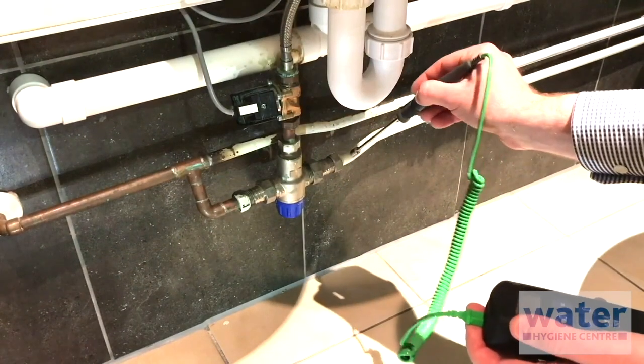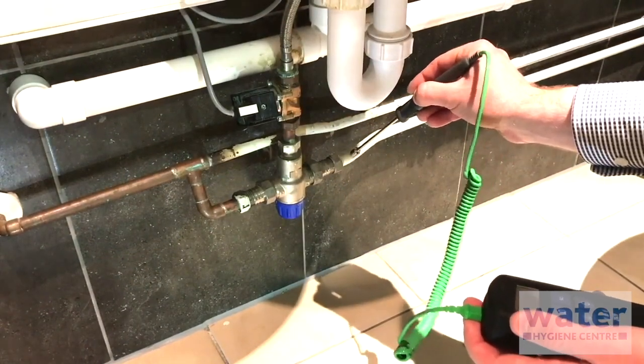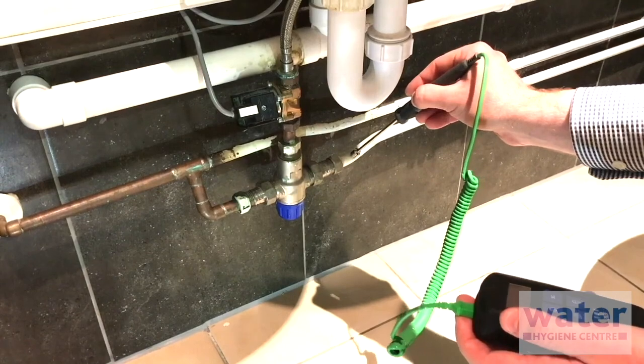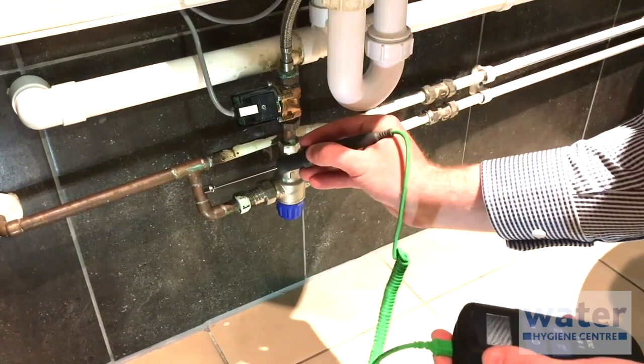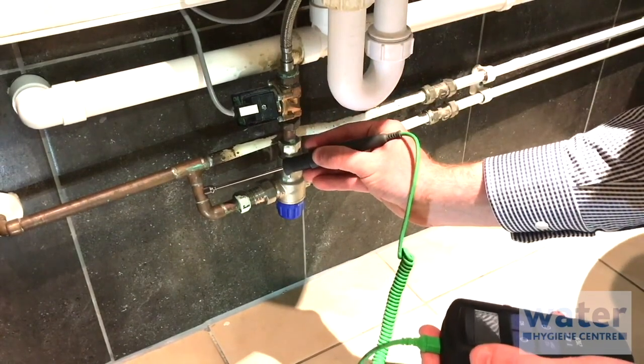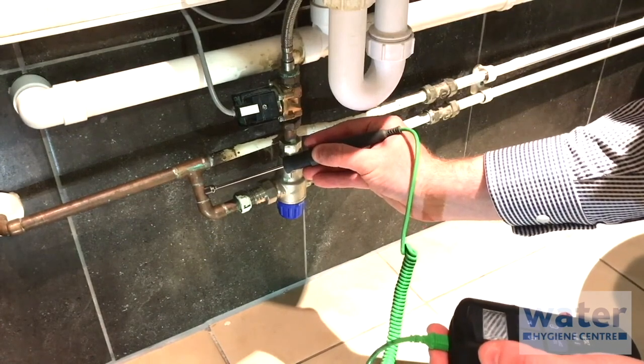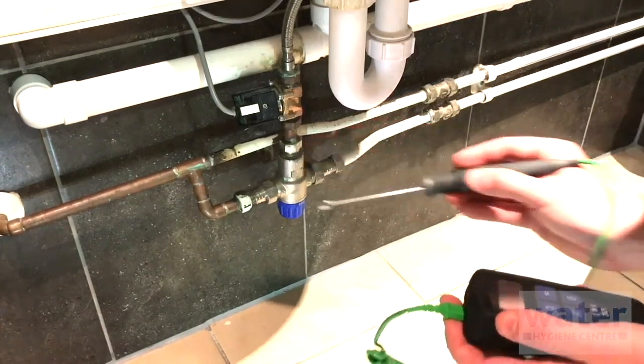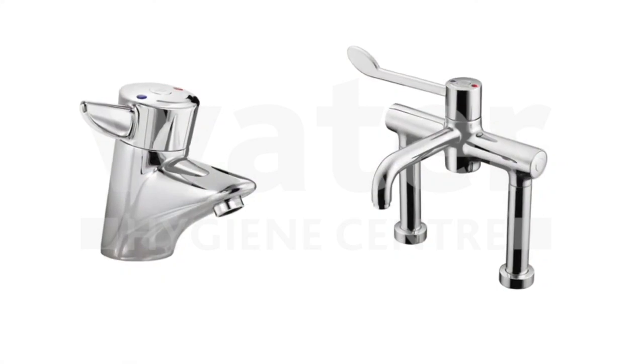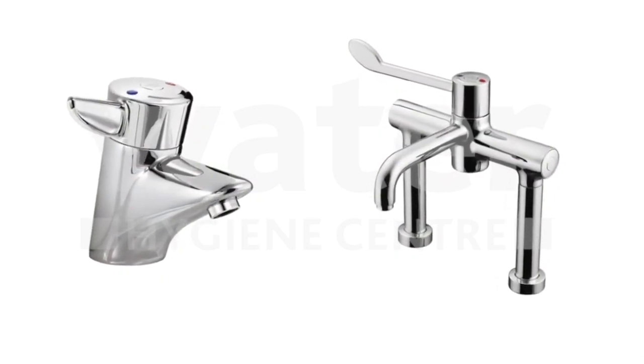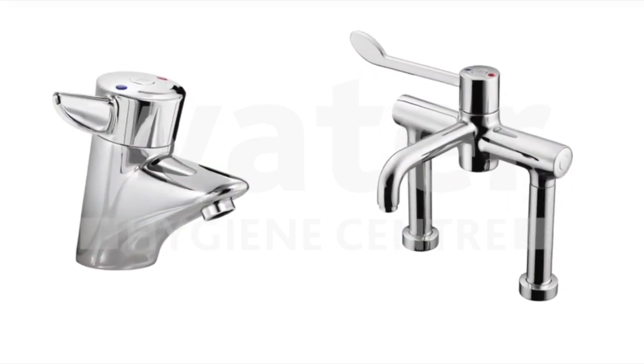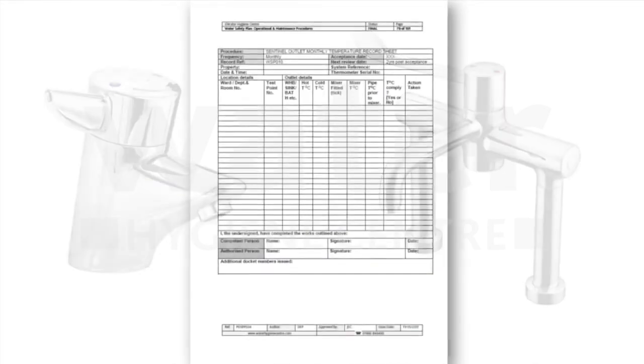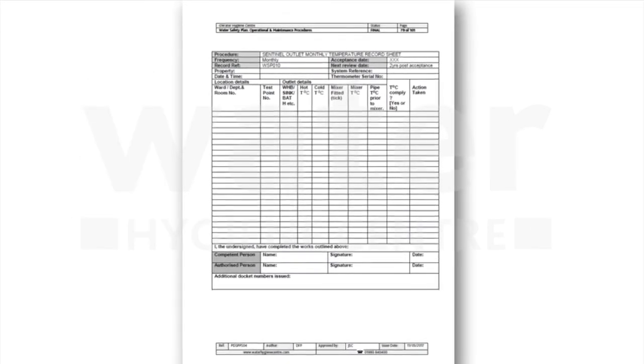Here you can see temperatures being recorded from the cold supply and the hot supply to the TMV. If required, heat sink grease can be used to help gather more accurate temperatures. The same principle can be applied to integral TMVs that are designed as part of a tap. As before, record your results on the monitoring form.